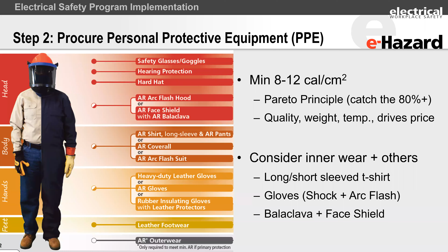Step 3 is the arc flash engineering study, because in step 2, what we said is, just roll out arc-rated clothing. And if you go between 8 to 12 calories per square centimeter, you are going to be addressing most of your hazards. The problem is you're not going to be addressing every single hazard. To get to that next level of excellence, you're going to need an arc flash engineering study. What is an arc flash engineering study?